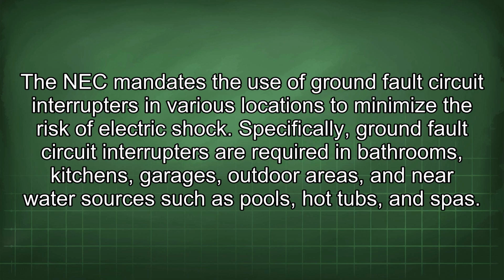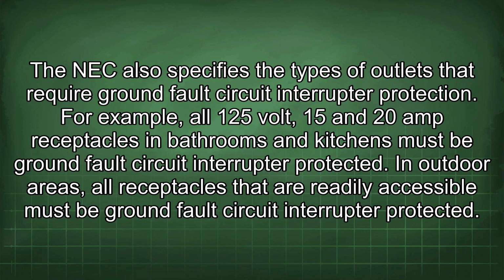Specifically, ground fault circuit interrupters are required in bathrooms, kitchens, garages, outdoor areas, and near water sources such as pools, hot tubs, and spas. The NEC also specifies the types of outlets that require ground fault circuit interrupter protection. For example, all 125 volt, 15 and 20 amp receptacles in bathrooms and kitchens must be ground fault circuit interrupter protected. In outdoor areas, all receptacles that are readily accessible must be ground fault circuit interrupter protected.